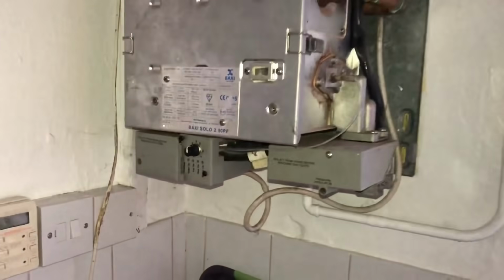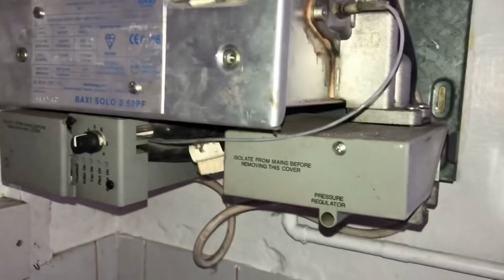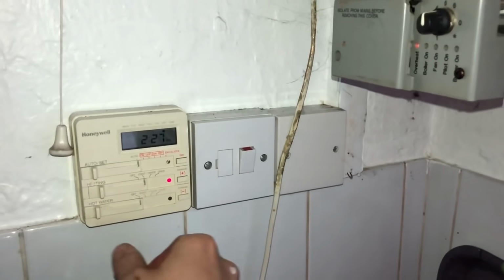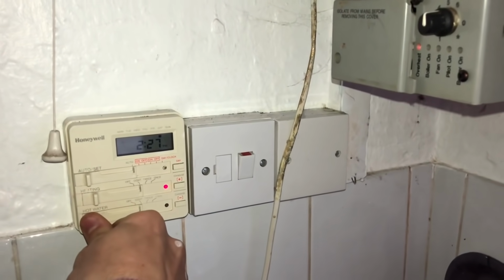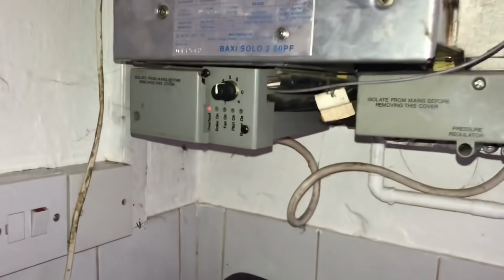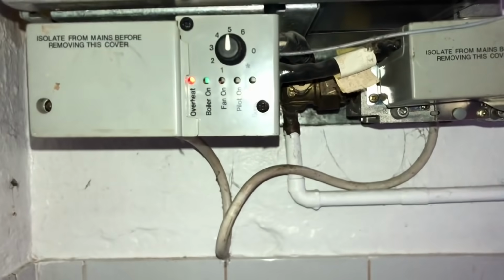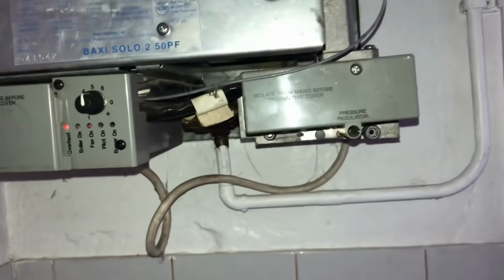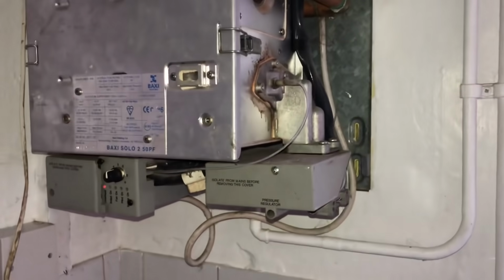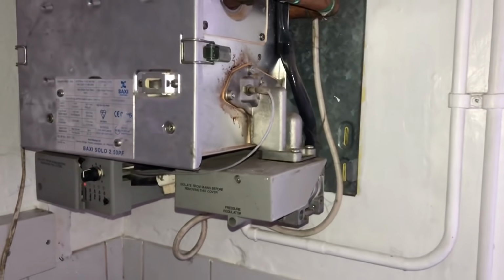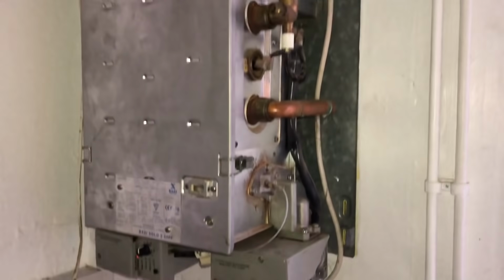This one was a little Saturday call out to a boiler with no heating and no hot water. When I got here, the tenants had turned the power off, so it's not been working for a few hours now, but she did tell me that it had an overheat fault. So you can see there the overheat neon's illuminated and lit. The boiler's cold because it's not been running, but the first thing we're going to look at is obviously the overheat stat, because that's what's telling the boiler it's overheated.